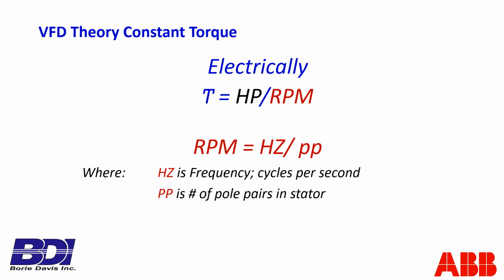The denominator in the electrical equation would be RPM. RPM is equal to frequency in hertz divided by the number of pole pairs in the motor. So frequency, hertz, cycles per second, divided by the number of pole pairs, PP for goodness sakes, is the number of pole pairs in the stator, which is the stationary part of the motor. That's where the electrical signal, the three-phase AC of voltage and frequency signals, are sent. The motor cables actually tie the electrical system into the stator of the motor.